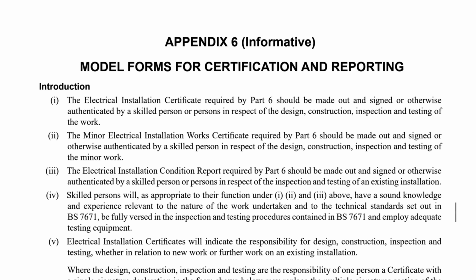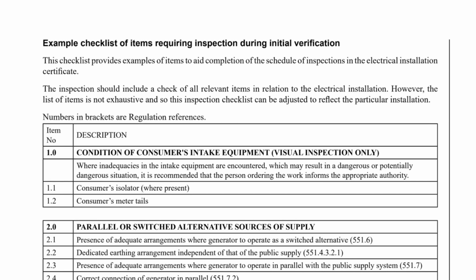Appendix 6 of BS 7671 gives us a model checklist of items to inspect on both initial verification and during periodic inspections. It informs us that item 1 is to check the condition of consumer's intake equipment and suggests that you check the consumer's isolator, where present, and the consumer's meter tails. It also advises that where inadequacies in the intake equipment are encountered, which may result in a dangerous or potentially dangerous situation, it is recommended that the person ordering the work informs the appropriate authority.